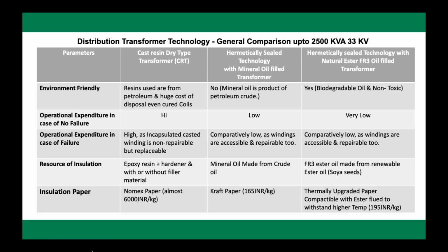When we are talking about this safety doesn't mean only human safety, safety to the environment too. And the environment safety, if you see, the most safest are the natural ester filled transformers. Why I'm saying so? Mineral oil, we all know, they are not environment friendly. And same is with the dry type transformer also. The resins and everything comes from petroleum. And if something spillage or something is there, it's a huge cost of disposal for resin. You have to send it to the incineration, burning. The similar activities what you do with mineral oil, but at least in mineral oil, you can filter it, use it, and only few quantities spent, left out or scrapped.